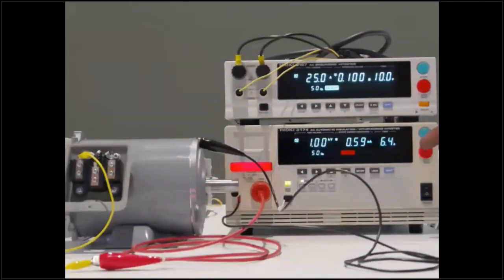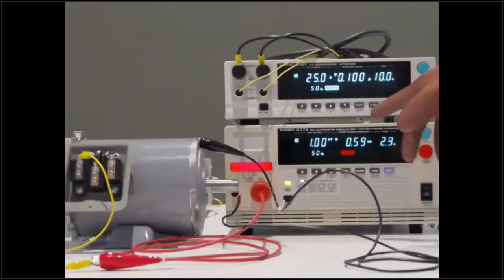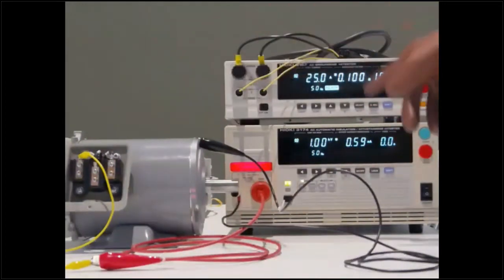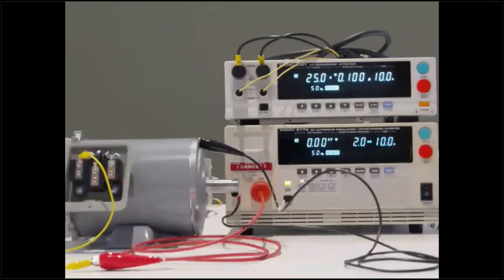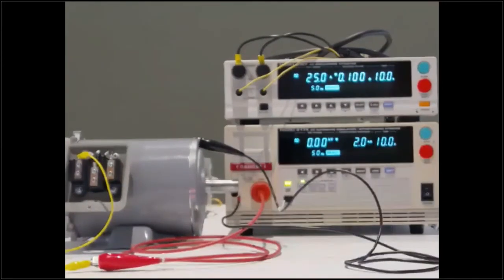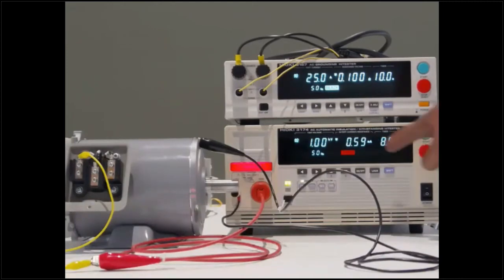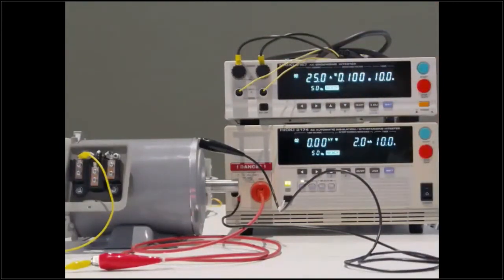Right now, as you can see, 10 seconds. This applies 1000 volts to this motor. In this time, the leakage current is just 0.59 milliampere, very very low, so this Hipot withstand test shows no problem.